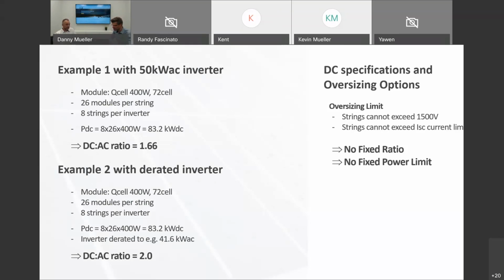for the system efficiency. And it's important to remember that Huawei will not void the warranty if you do large oversizing, unlike most other inverter companies which will void your warranty if you go 2:1. It's specifically allowed to size to those two factors, 1,500 volt again, and the short circuit current limit of 30 amps per MPP tracker.